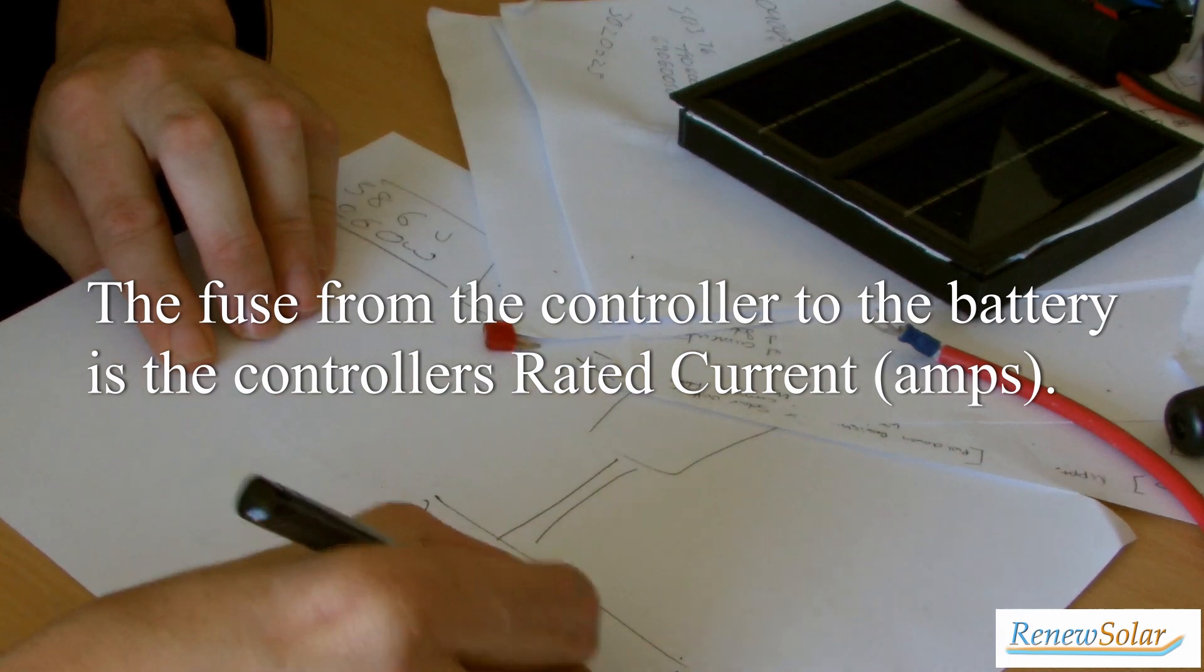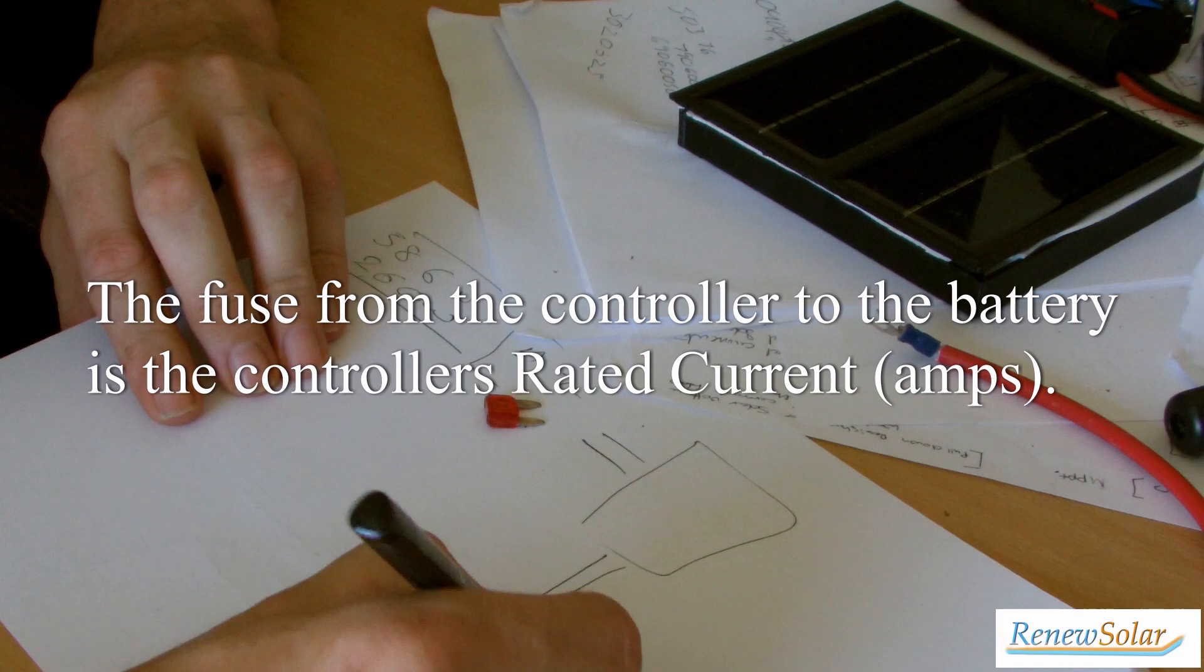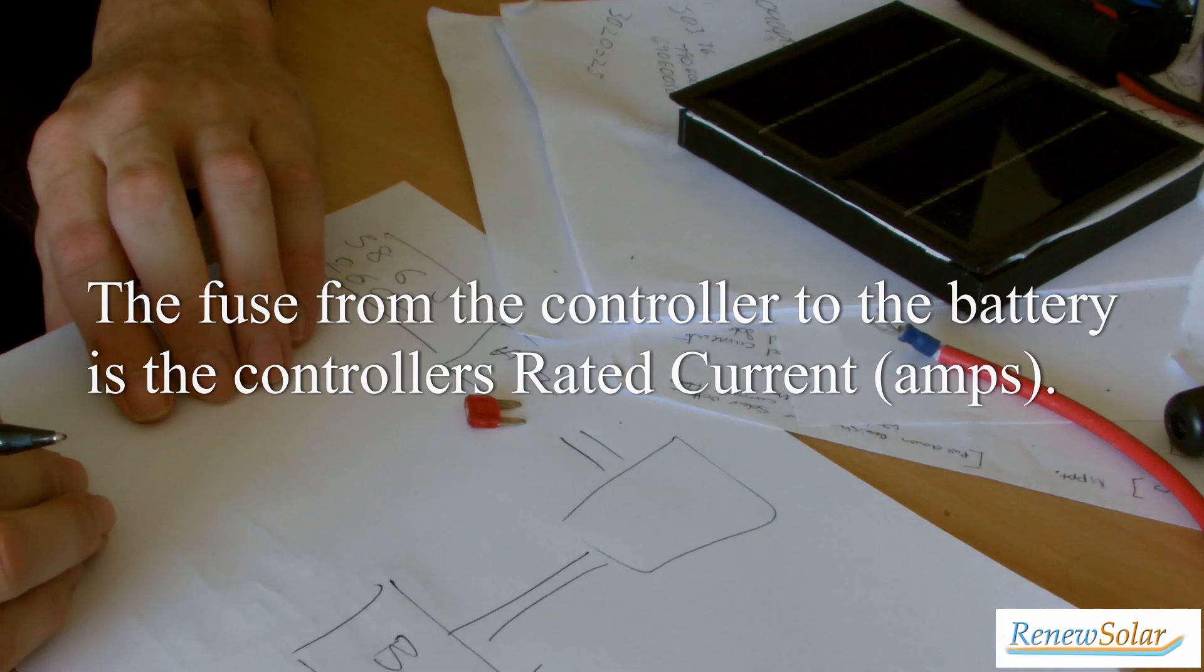Now there's no connection anywhere else. You'll have your battery. Let's zoom back out a little bit. You have your battery bank there and that can be 12 or 24 volts or it could be 48 volts. It depends on really how you're doing it. So what we have here is essentially we want to connect our solar panels via a fuse to the charge controller.